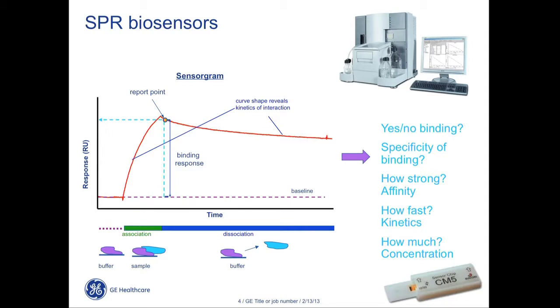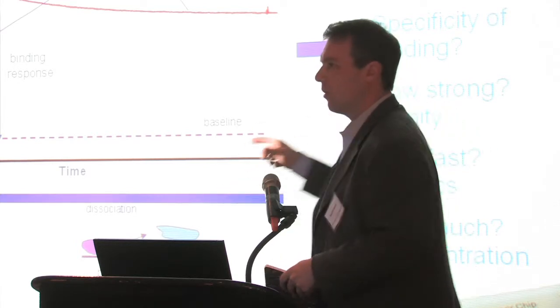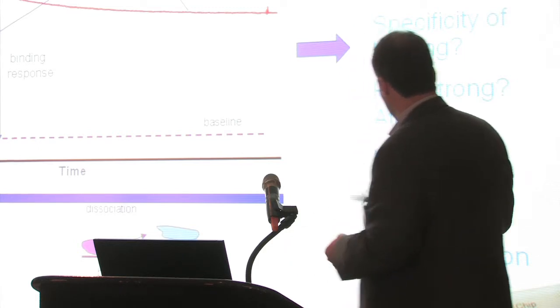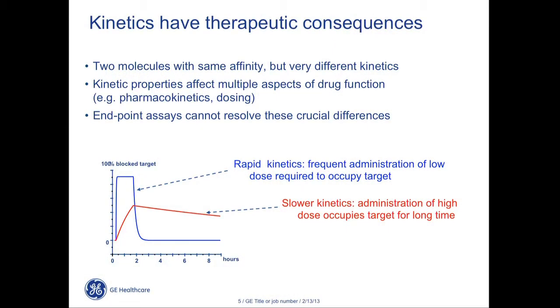From the sensorgram we directly obtain on and off rates and affinity, which is derived from their combination. Based on assay design and what is immobilized on subsequent flow cells — the system has four flow cells — you can also understand the specificity of binding for a particular protein or construct. The same methodology is used to derive the active concentration of a molecule. When we look at affinity alone, that value is a combination of on and off rates, which could derive from very different contributions from those two factors.